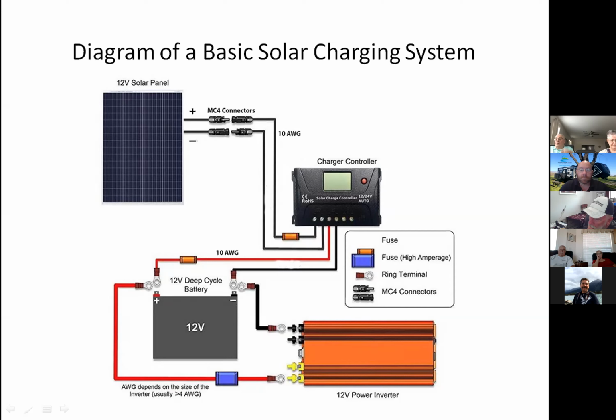Working down the system, those wires are 10 AWG, or 10 gauge, which is very typical in most solar charging systems. The next item is that orange little box, which is a fuse. You have to have the system fused in case you get into a runaway, high-current condition—the fuse will pop and protect your system and your coach.